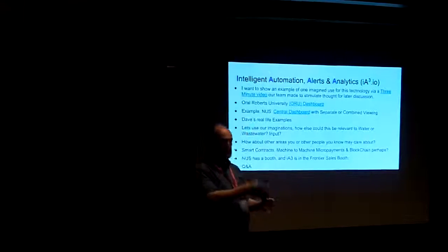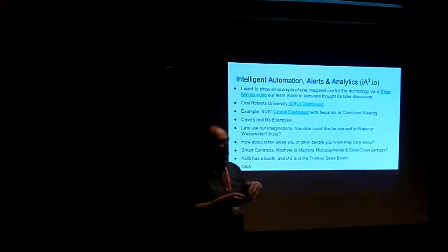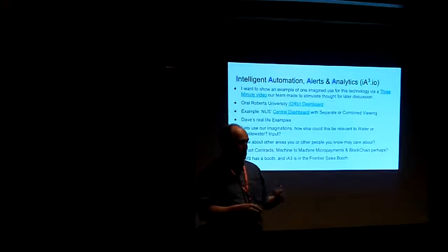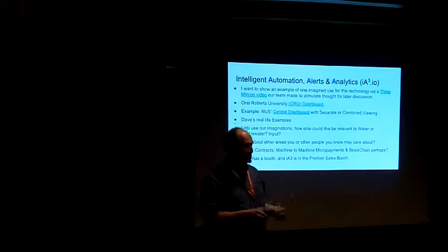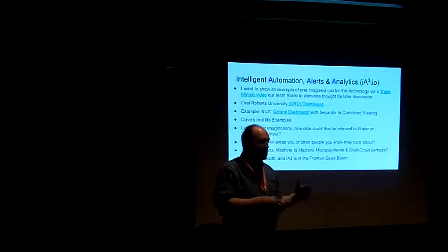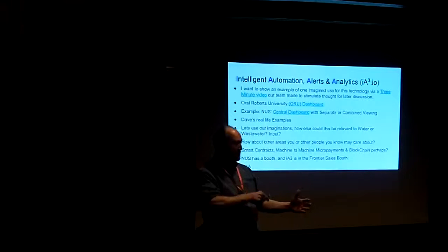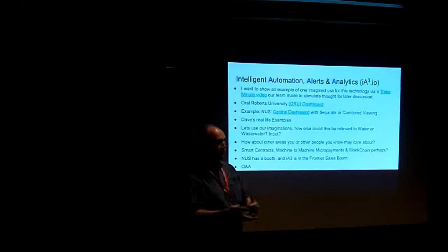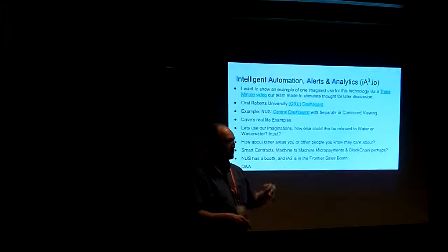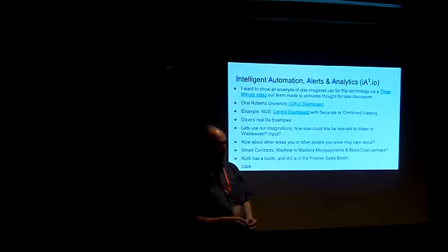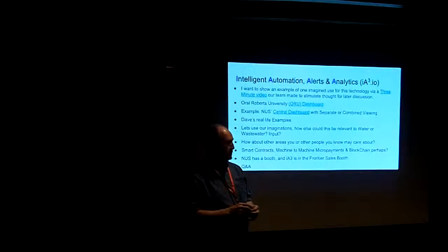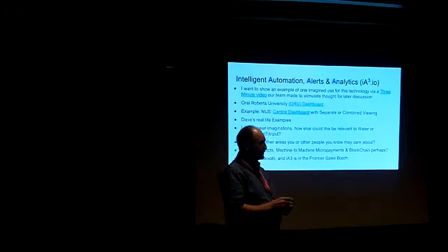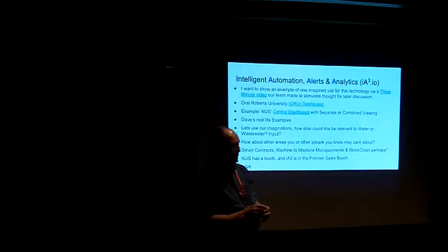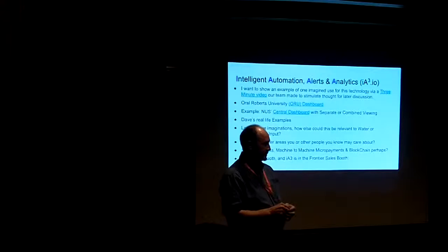Those are the kinds of examples and things you can't anticipate, talking to that VFD wasn't necessarily expected to be that valuable. But if you have it, it's there to think about after the fact, and it can be used in ways you never imagined when you put it in. So that's what resulted from the Modbus communication, being able to talk both ways and give commands to that VFD, telling it to raise its target pressure.